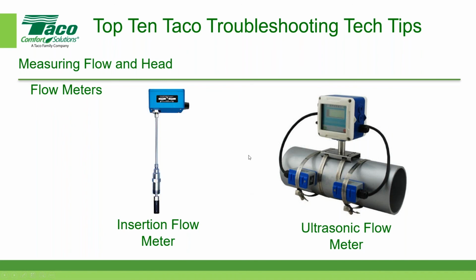Flow meters. The two types that we talked about: one is a permanently installed insertion flow meter. This particular one that's in blue is an Onicon flow meter. We have several of these at the factory that we use for keeping track of our hot water and chilled water systems. And then the other type, which is typically not a permanent installation but is used for troubleshooting, would be an ultrasonic flow meter, sometimes referred to as strap-on, and you can see the straps that are connected to the pipe. And usually these guys require a substantial amount of straight run of pipe to get an accurate reading.